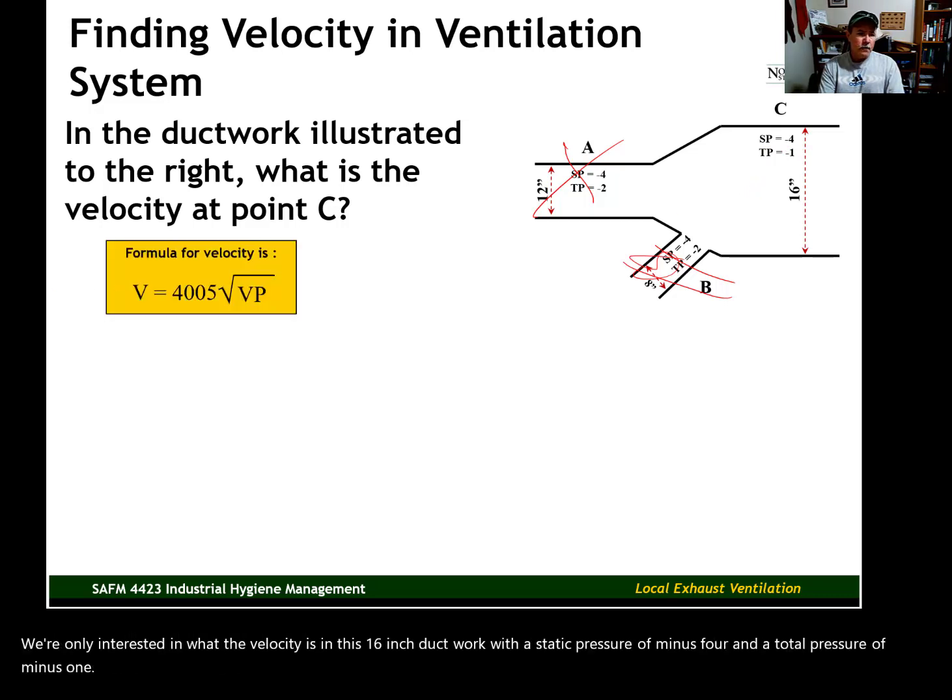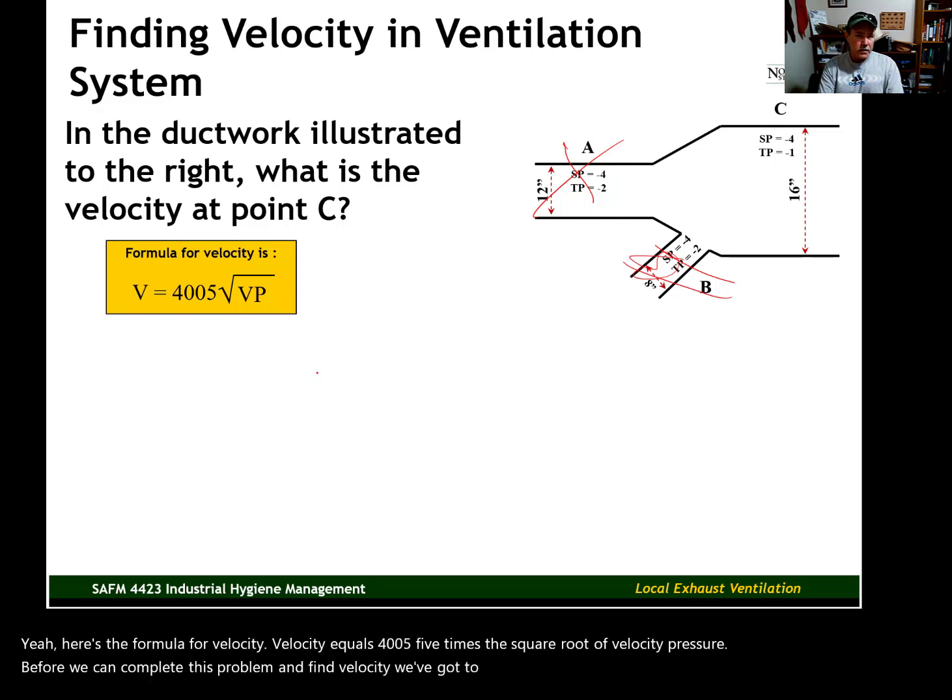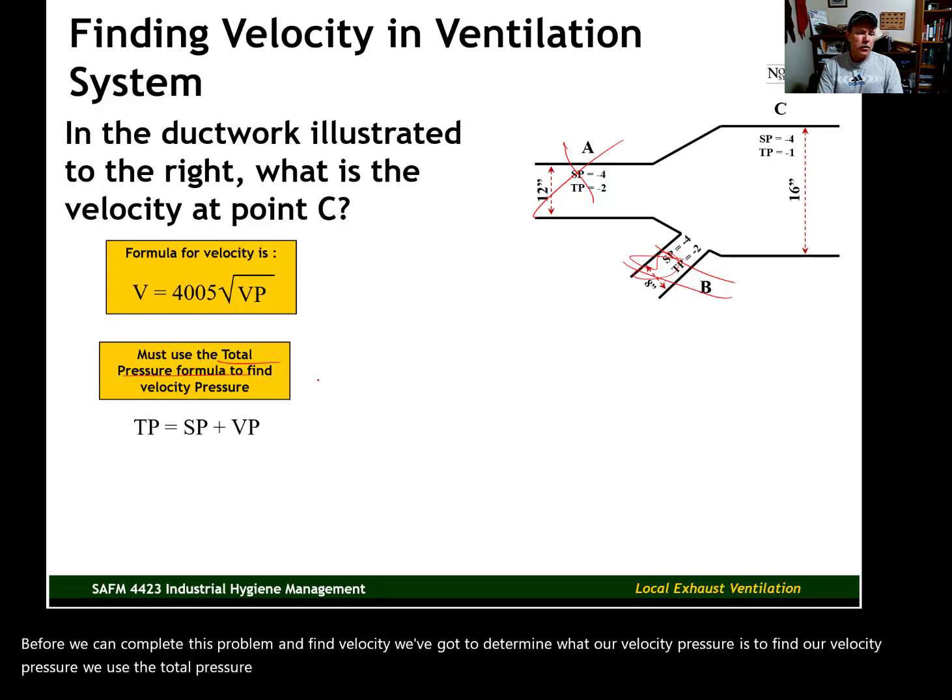Here's the formula for velocity. Velocity equals 4,005 times the square root of velocity pressure. Before we can complete this problem and find velocity, we've got to determine what our velocity pressure is. To find our velocity pressure, we use the total pressure formula that I showed you in a previous session.